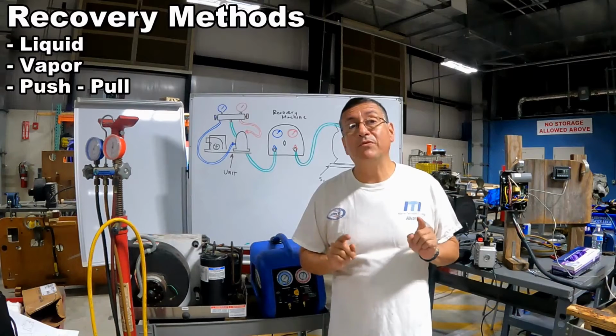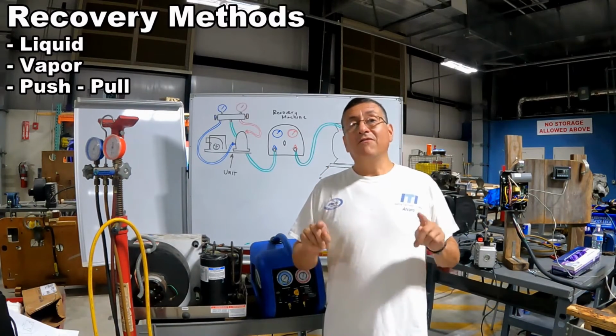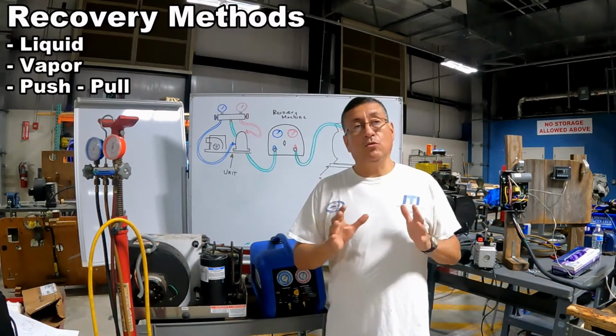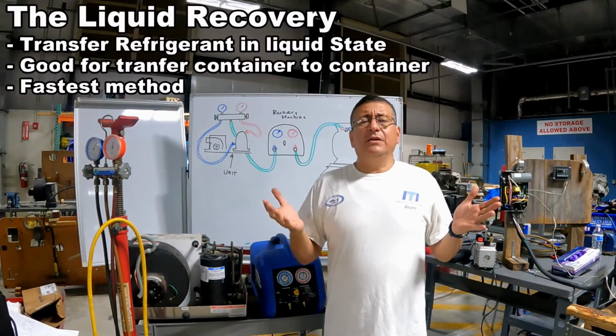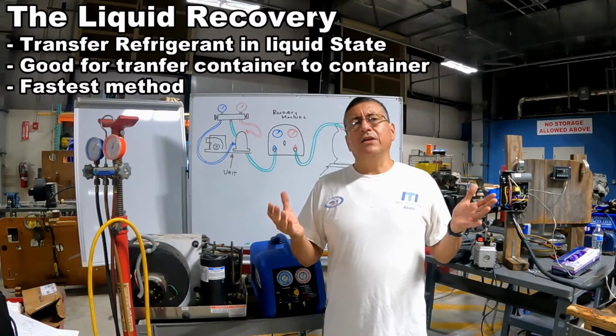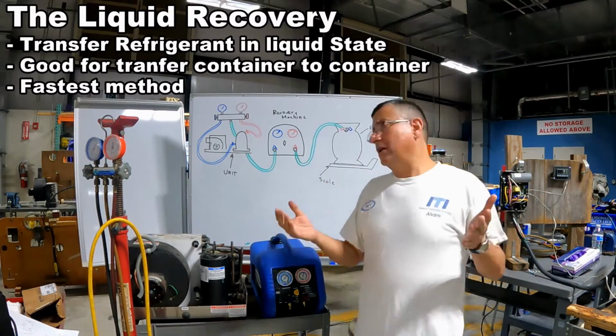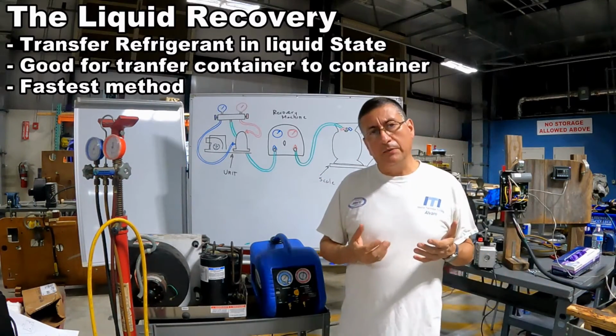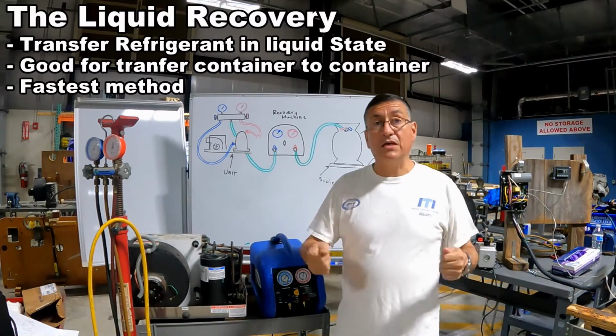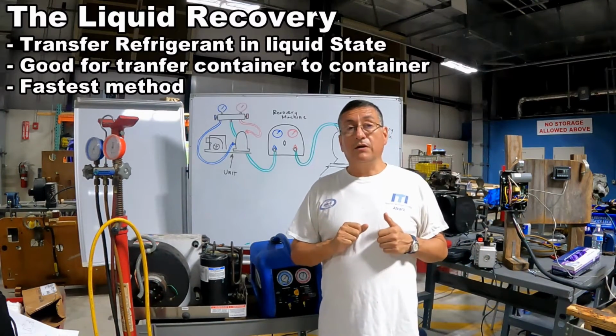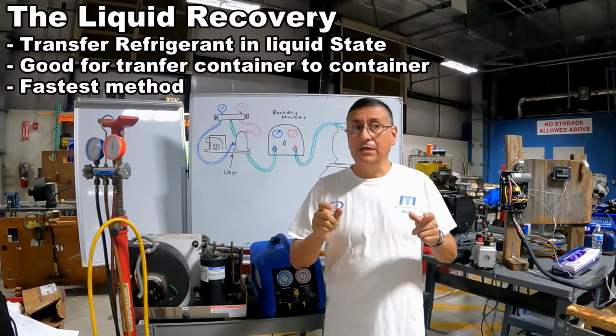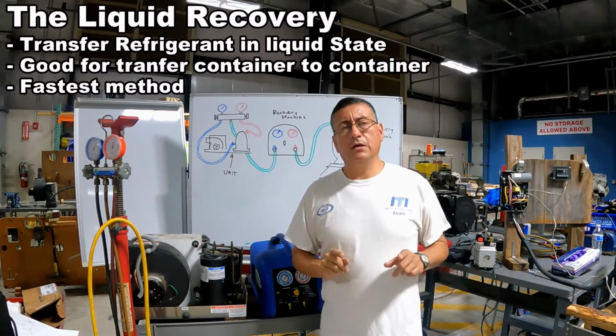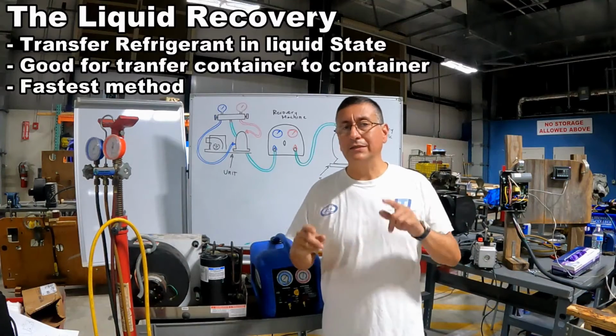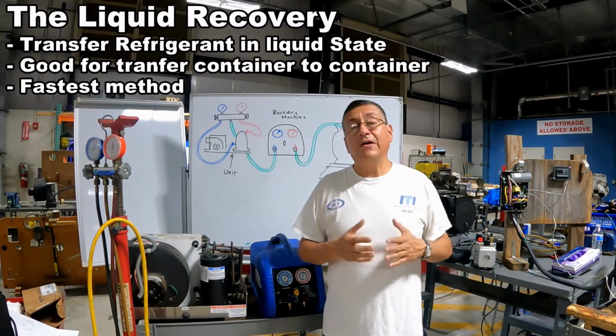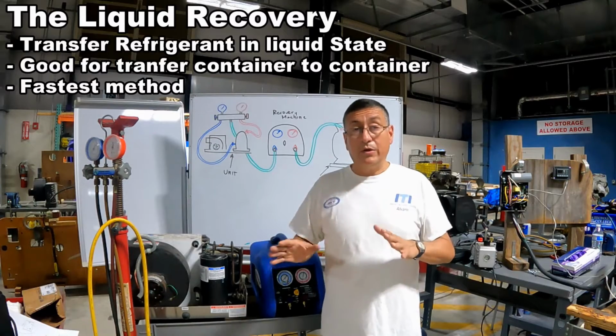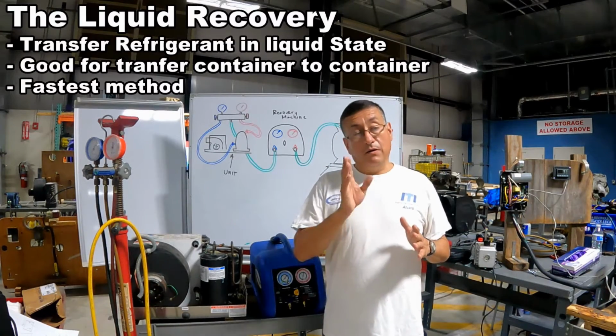Basically, there are 3 types of methods: the liquid method, the vapor method, and the push-pull method. The liquid method recovers the refrigerant in liquid state and transports the refrigerant in liquid state into the cylinder. It is the fastest method used to recover refrigerant. It's not the most common, it's the fastest. It's good when you need to transfer refrigerant from cylinder to cylinder. This is excellent. And of course, it's the fastest method.